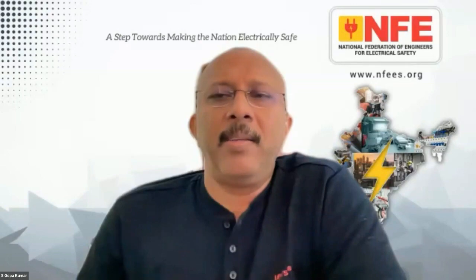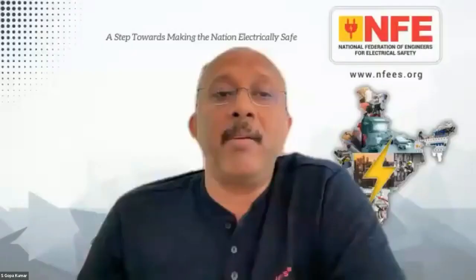I just wanted to add something. So the standard Mr. Vajari is referring to, I think it's referring to the fact that you shouldn't use a gas pipe, a steam pipe, a sprinkler pipe, or a humidifier as a means of earthing. So that's as an electrode. That obviously you're not supposed to do in any case. So that's similar to what 7671 says as well. You're not supposed to use those as an electrode. Yes, no, you shouldn't be. Although we do by default equipotential bonding anyway. Yeah.